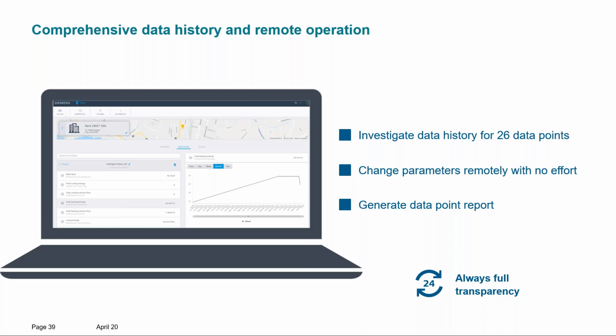Or you can go down to the air handling unit level and have the delta T of the last month available as a report, and see where delta T does not match the operation conditions. Can I even improve my delta T setting in the system, increase the delta T limitation from 6 to 7K without major comfort issues, and so optimize the system? So a direct cloud solution bypasses the complicated, maybe also service intensive building management system.